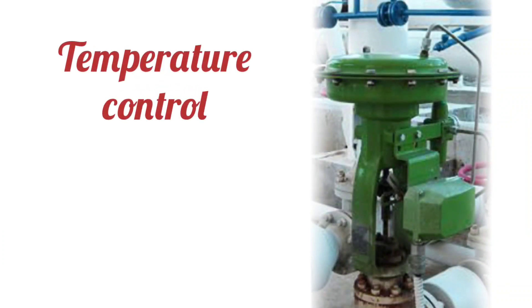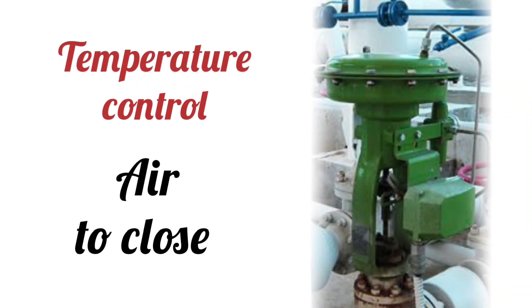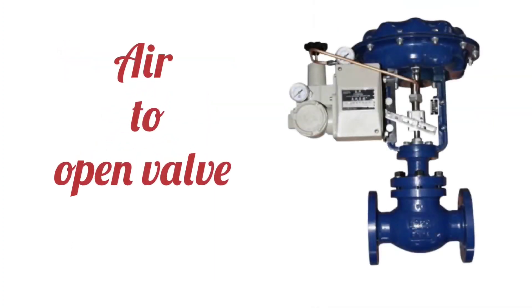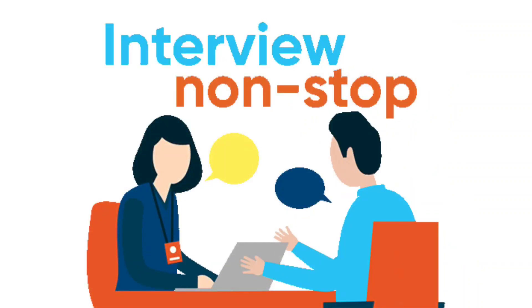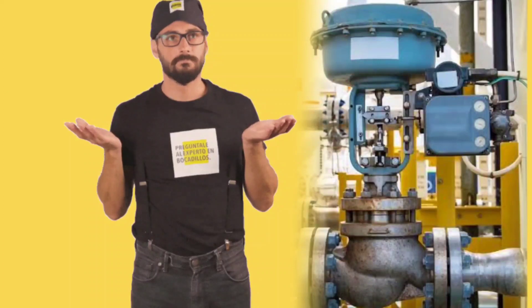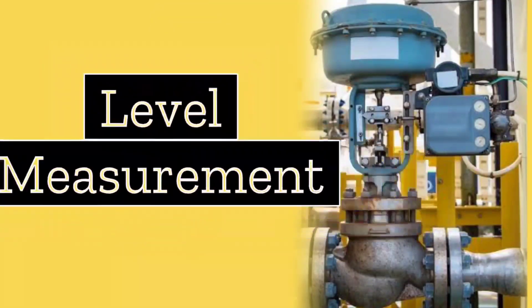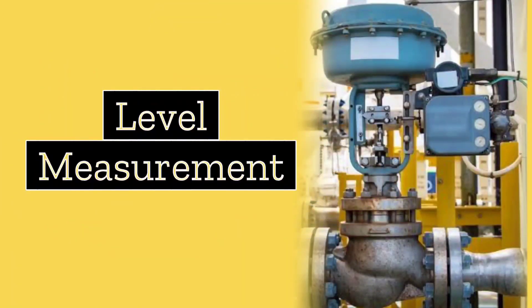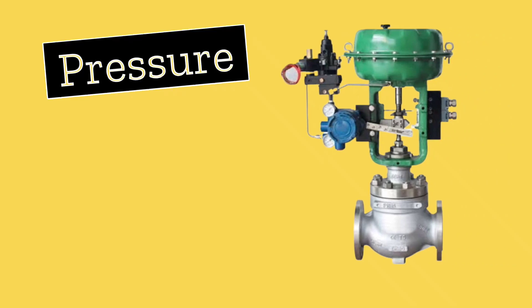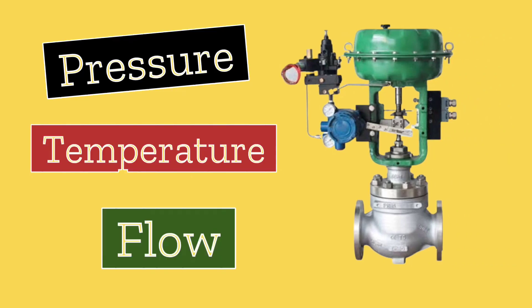Sometimes, air-to-close control valves are also used for temperature control. Apart from this, air-to-open valves are used in other places. Usually, air-to-close control valves are used for level measurement, and air-to-open control valves are used for pressure, temperature, and flow measurements.